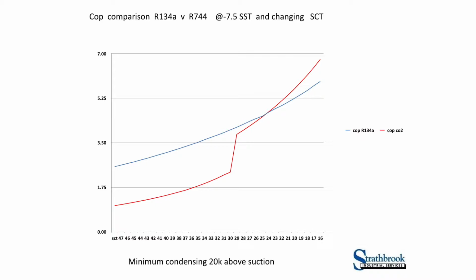So there's the one graph that I will show you, which is a comparison of the energy efficiency of R134A compared to CO2. As you can see, the blue line is fairly level, and as the condensing temperature rises over here on the 47 degree end of town, the energy efficiency of the 134A falls away, but nothing like the fall in the CO2 system. So we needed to keep the condensing temperature of the refrigerants as low as possible.